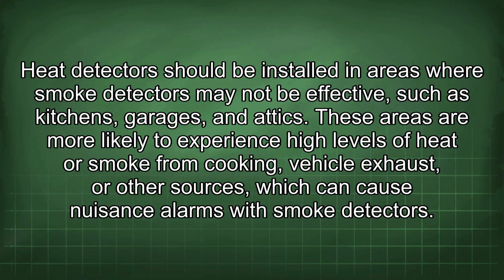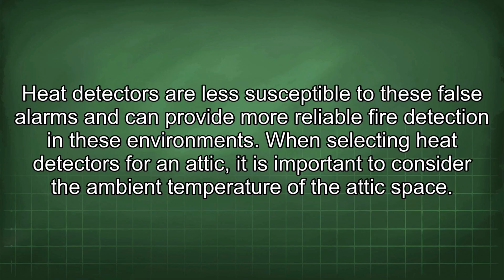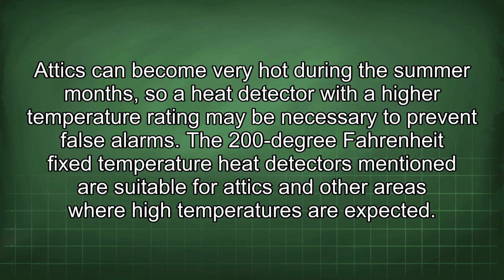These areas are more likely to experience high levels of heat or smoke from cooking, vehicle exhaust, or other sources, which can cause nuisance alarms with smoke detectors. Heat detectors are less susceptible to these false alarms and can provide more reliable fire detection in these environments. When selecting heat detectors for an attic, it is important to consider the ambient temperature of the attic space. Attics can become very hot during the summer months, so a heat detector with a higher temperature rating may be necessary to prevent false alarms.